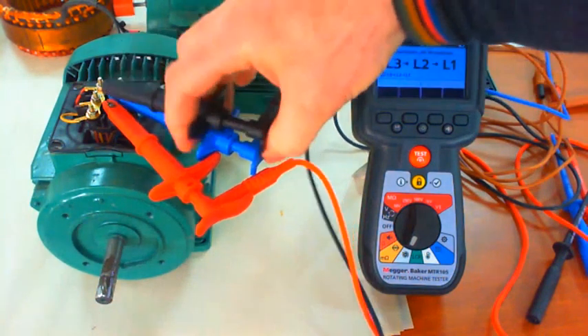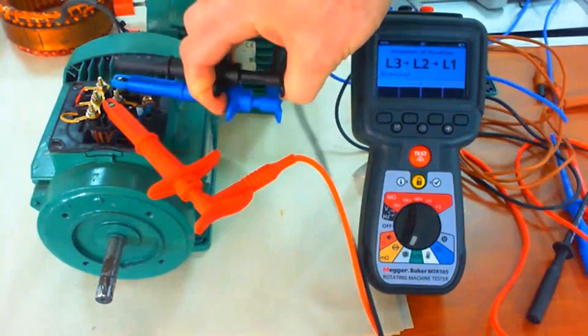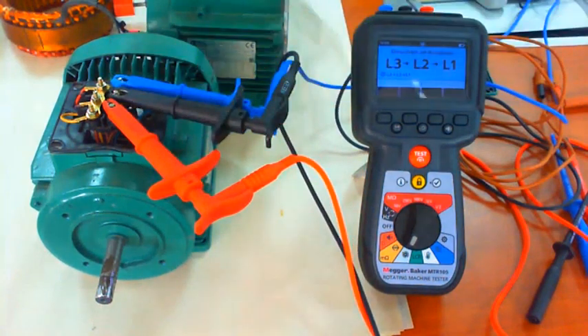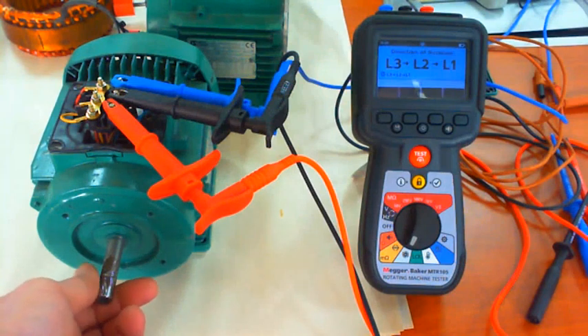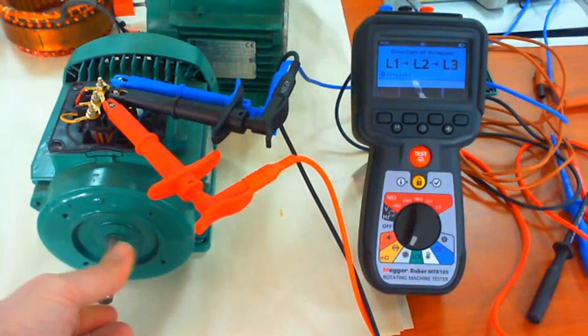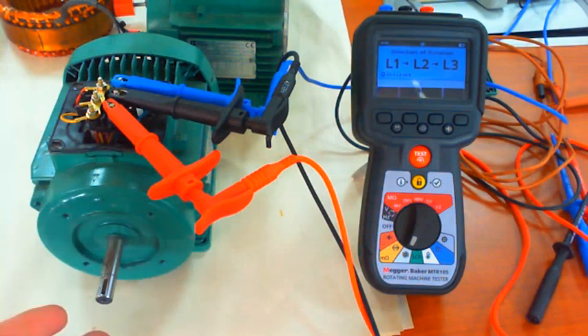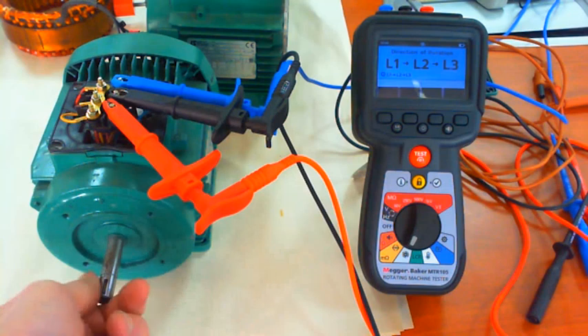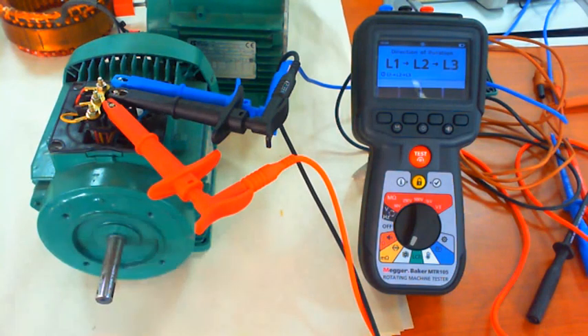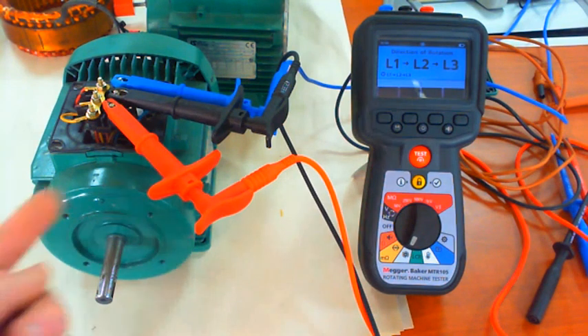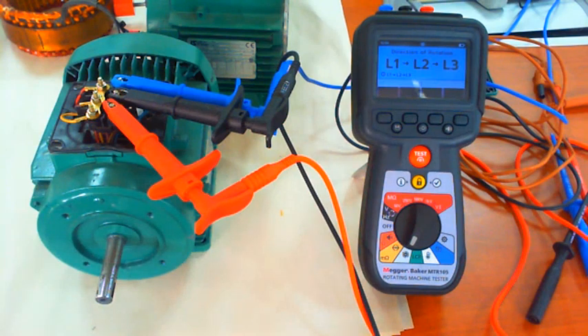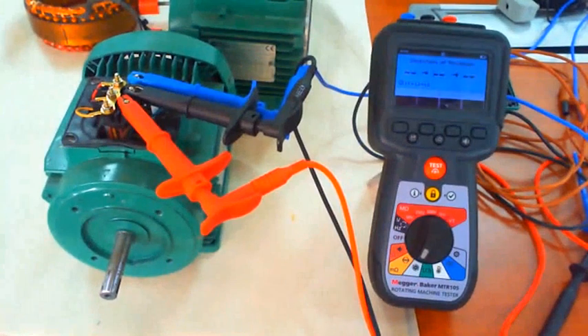Okay, so it's pretty simple. We just need to check our power supply rotation. And if we've got on the power supply L1, L2, L3, we then come to the motor, we connect our leads, red, black, blue, we turn the shaft in the direction we want. And if we get the same L1, L2, L3, we know that when we connect that power supply into the motor and press the button, the motor is going to turn in the clockwise direction. Okay, that's about it for the demonstration.